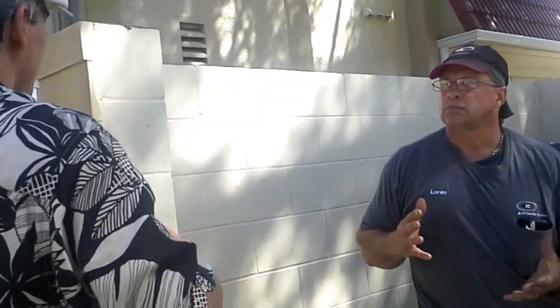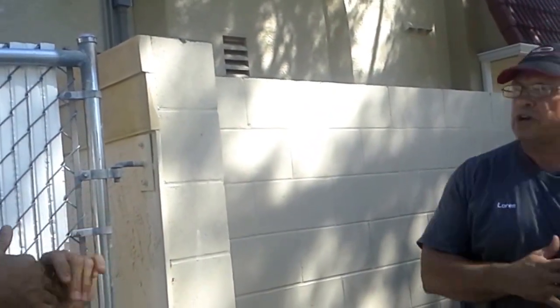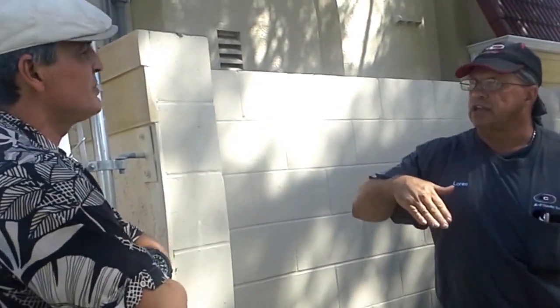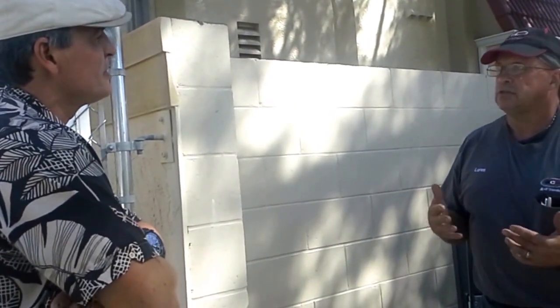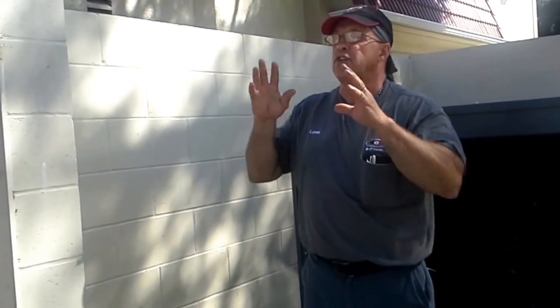With or without a load? With the load transfer. I don't know if he understands the load. That's with the power off. It's okay. The load is we use your building load to put it on the generator and carry that load. Your transfer switch actually switches and carries that load. You would have about a quarter of a second of power outage. For most cases, it doesn't interfere with anybody. If you're looking at the lights, you could actually see them blink, but if you're not paying attention, you wouldn't even know.